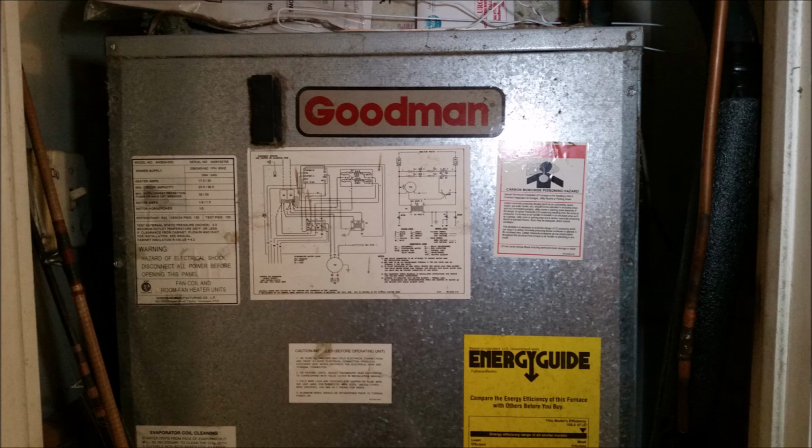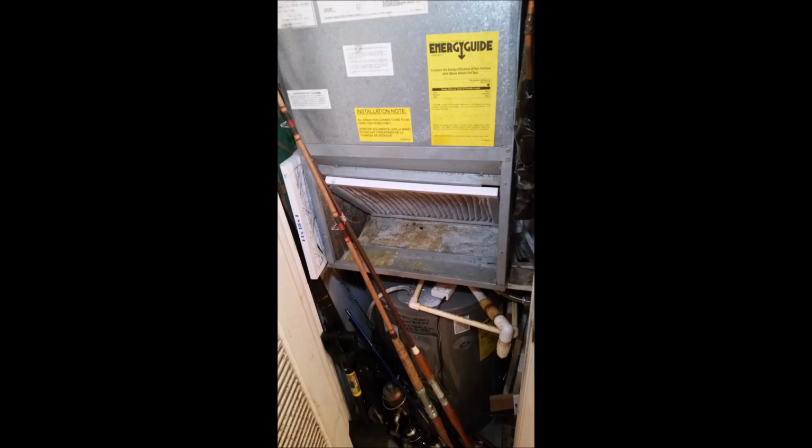The airflow wasn't right. So I was able to just clean those louvers and then leave the door open a crack and increase the airflow to my air conditioner again, and now it's no longer icing up. So I got real lucky. Maybe you'll get lucky too.